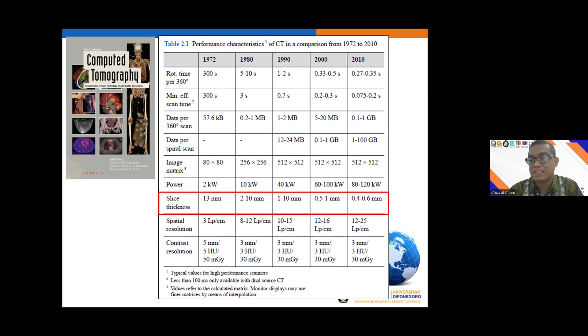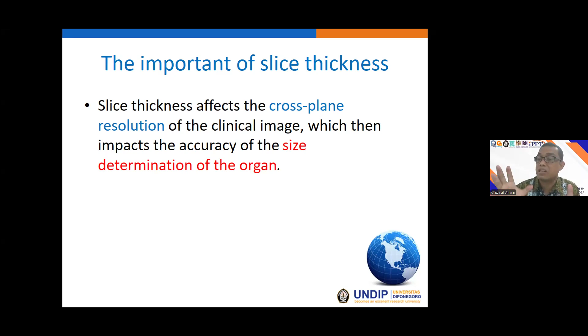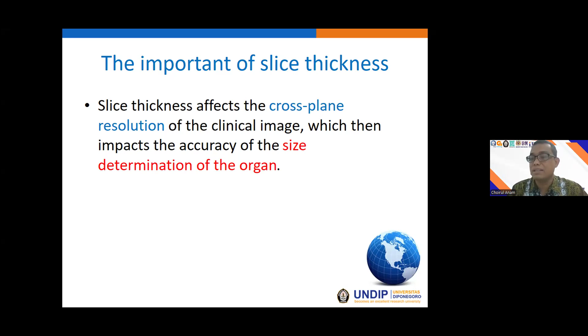Okay, and as we already mentioned, the slice thickness affects the cross-plane resolution of the clinical image, which then impacts the accuracy of the size determination of the organ. So if we want to get better image resolution in the Z-axis, we should choose a very small slice thickness. But as already mentioned, the image will be noisy. If we set the slice thickness wider, the image is less noisy, but the spatial resolution is compromised. So we can set the slice thickness depending on our clinical setting. For example, if we want a very high spatial resolution image of the lung, we should set the slice thickness smaller. But if we want a less noisy image, we can set a wider slice thickness. So in the clinical setting, we should choose the slice thickness wisely.